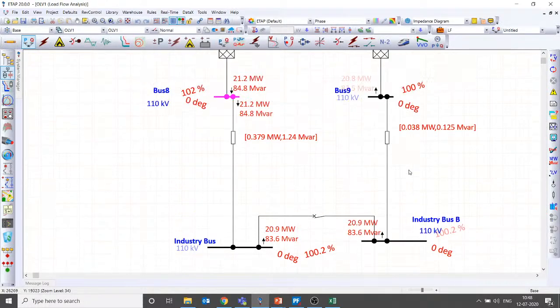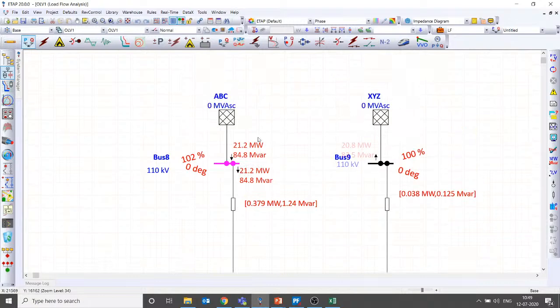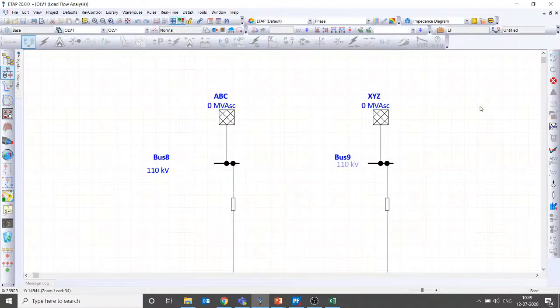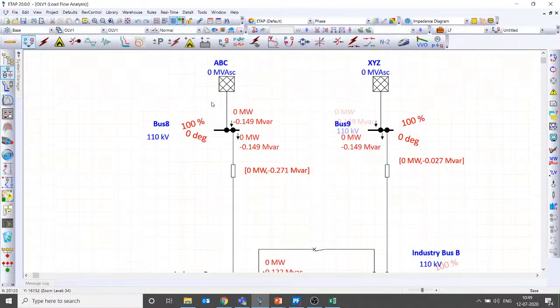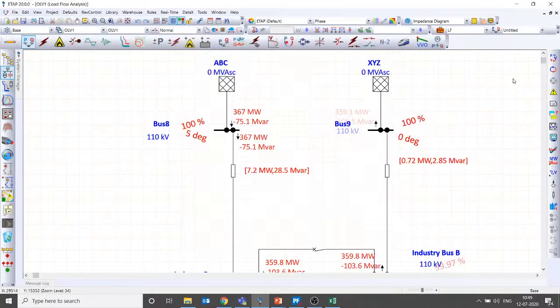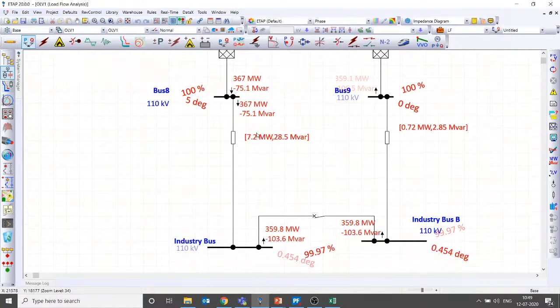So if you are an industry, you cannot really connect two different sources at your premises. You are not allowed, you are not authorized, and if you do that, then there will be an uncontrolled power flow. This uncontrolled power flow is not just because of the voltage, it could be because of the angle also. For example, if I keep the voltage at 100 and the angle at 0, the power flow will be almost negligible, 0 megawatt. But assume that the angle is more, for example if the angle is 5, that's huge power. You can see there is an enormous power flowing via your industry substation.